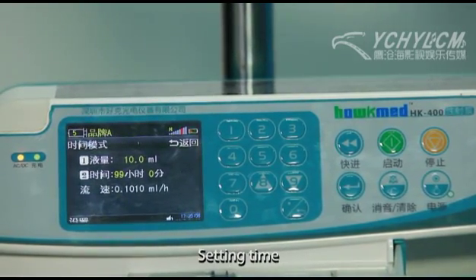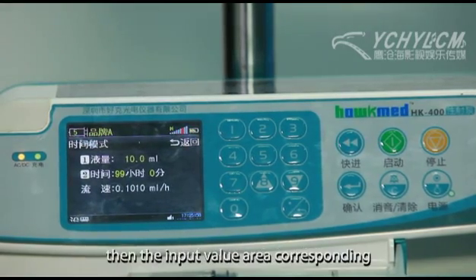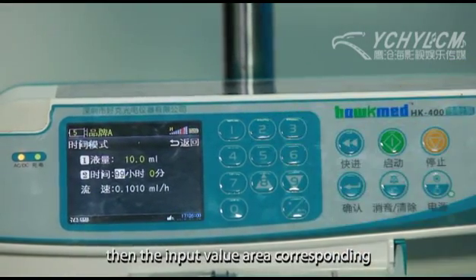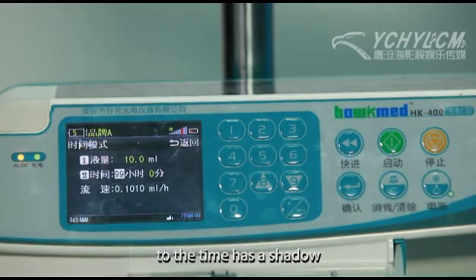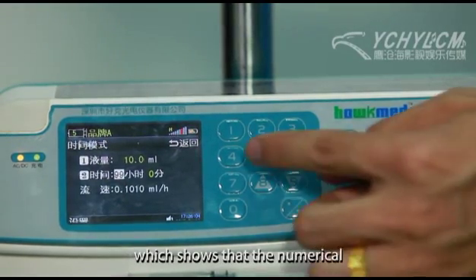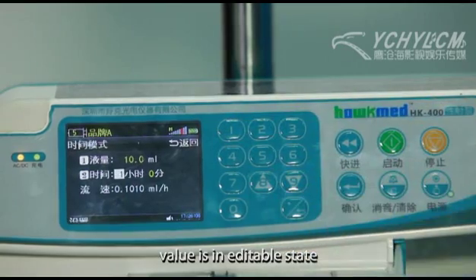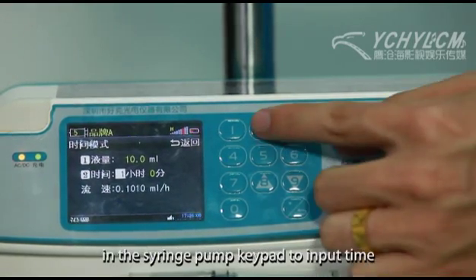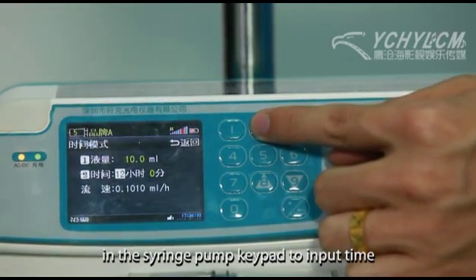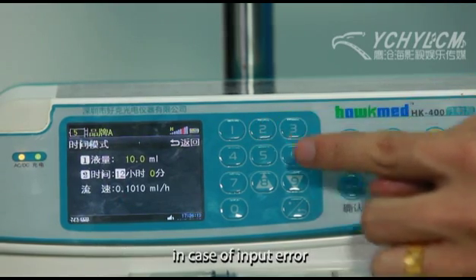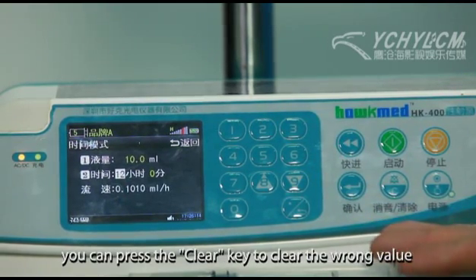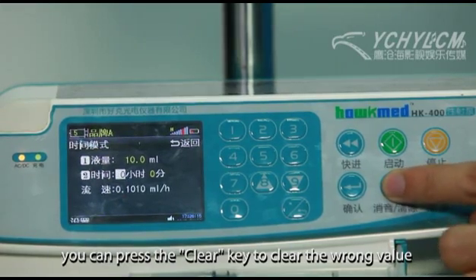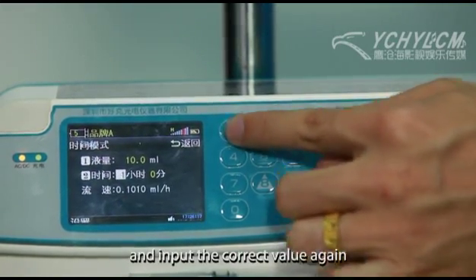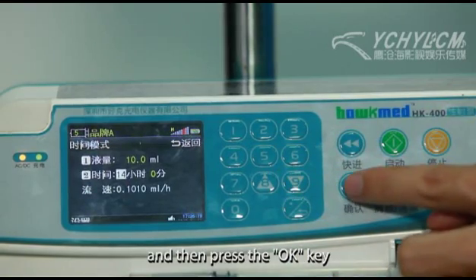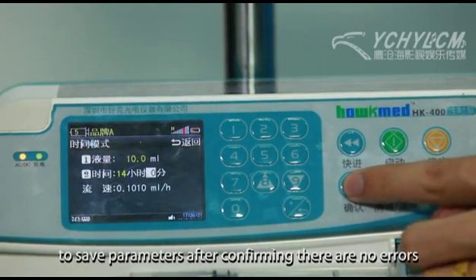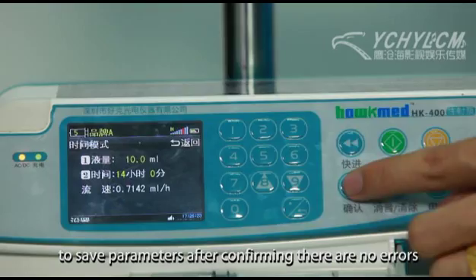Setting time. Press the numeric key 2, then the input value area corresponding to the time has a shadow, which shows that the numerical value is in editable state. Press the corresponding number on the syringe pump keypad to input the time. In case of input error, you can press the Clear key to clear the wrong value and input the correct value again, and then press the OK key to save parameters after confirming there are no errors.